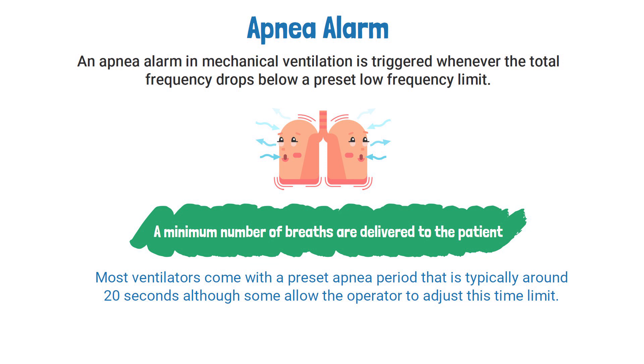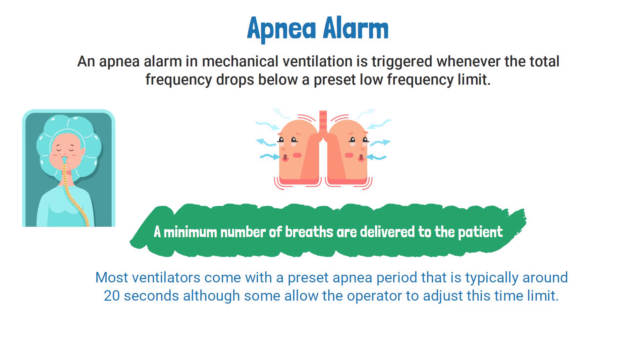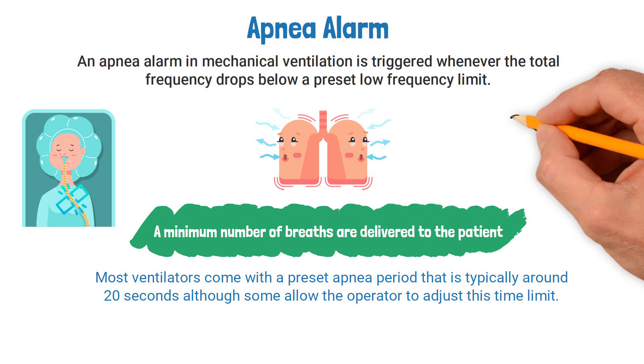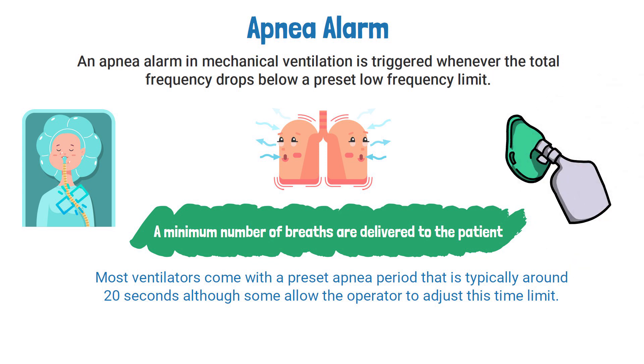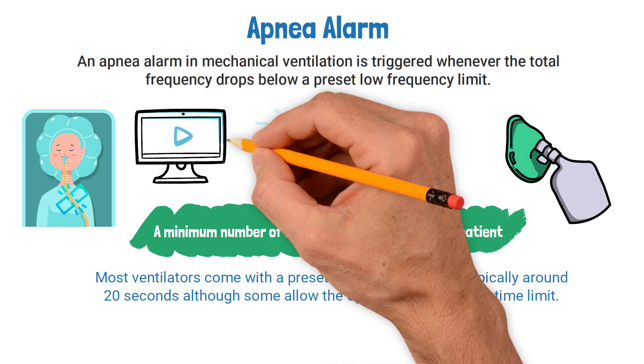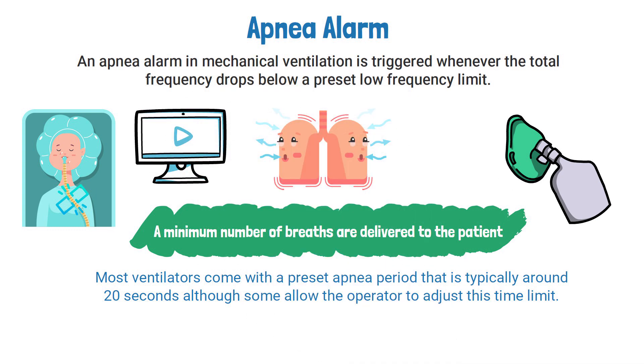The activation of an apnea alarm most commonly occurs whenever there is a disconnection in the circuit from the ET tube. When this occurs, the respiratory therapist must ensure that the patient is being ventilated by delivering manual breaths until the source of the disconnection is identified.